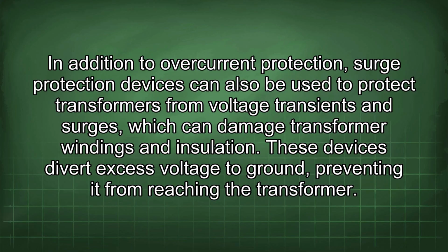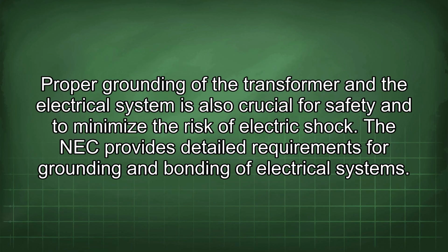In addition to overcurrent protection, surge protection devices can also be used to protect transformers from voltage transients and surges, which can damage transformer windings and insulation. These devices divert excess voltage to ground, preventing it from reaching the transformer. Proper grounding of the transformer and the electrical system is also crucial for safety and to minimize the risk of electric shock. The NEC provides detailed requirements for grounding and bonding of electrical systems.